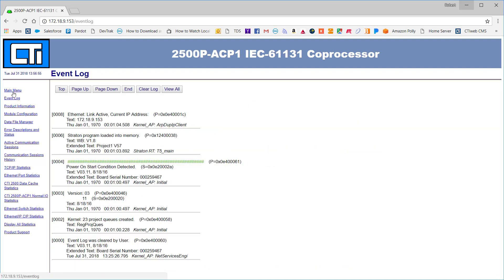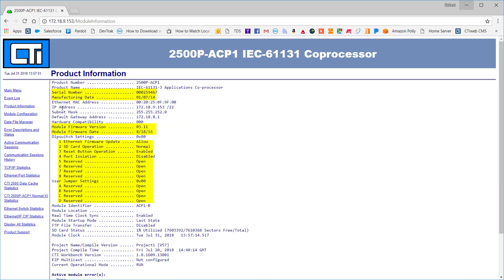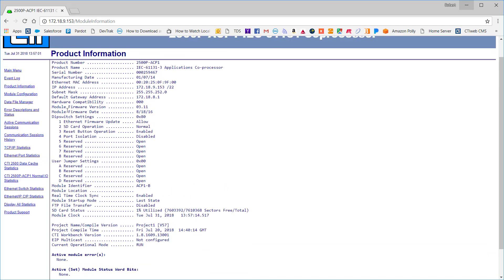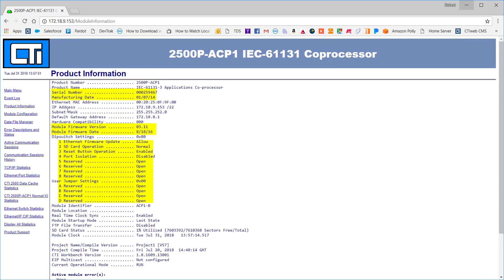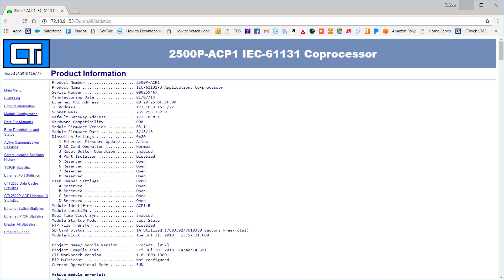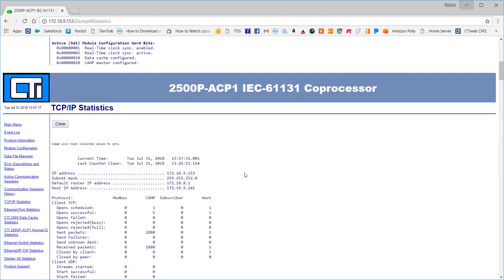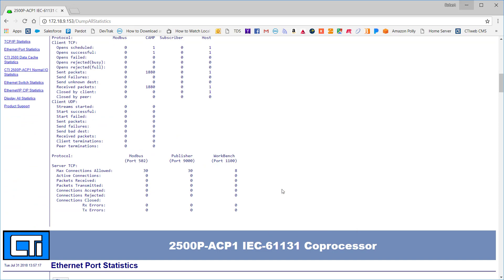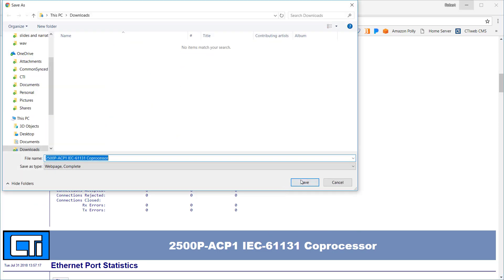The event log page records significant events that occur during the startup and operation of the module. The product information page contains information about the module hardware, firmware, and current configuration. The module configuration page includes user settings for parameters such as IP address, startup operation mode, and system time source. There are many other pages which are specific to each target device, including extensive debugging information about network and communications activity. The display all statistics page includes a complete set of diagnostic information which will be needed by CTI technical support if you call for help. Most browsers will allow you to save the page, which can then be emailed to your support contact.